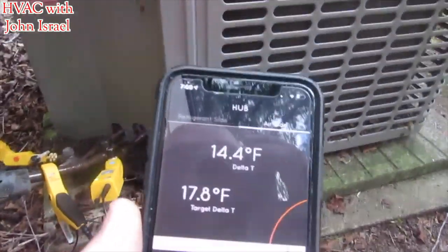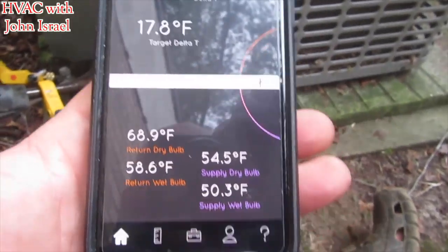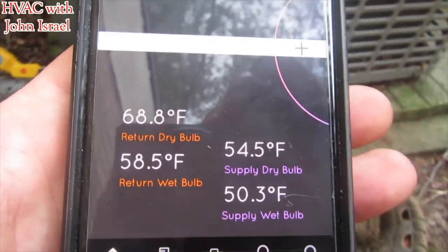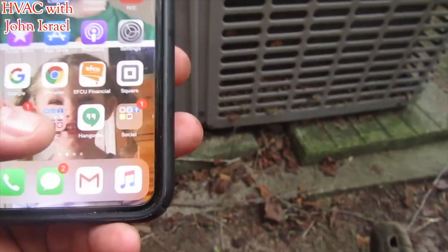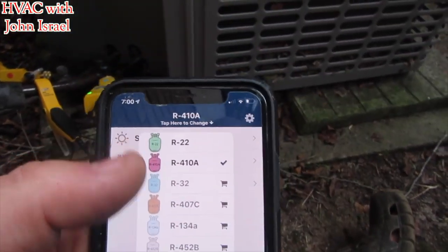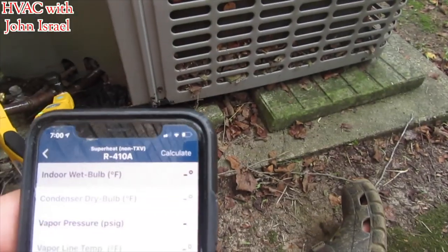Let me verify if I have a TXV or a piston real quick. After verification we're using a piston. Our temperature split is not close — it's about three degrees off. There's our wet bulb reading. So I'm going to go into check and charge — 410A, superheat, non-TXV. Our wet bulb is 58.